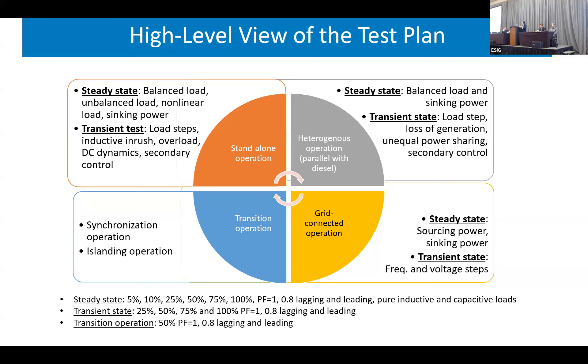We also have grid-connected operation. Industry wants to see how grid-forming inverters behave when connected to the grid. So we did a lot of grid-connected tests — how to control and dispatch the grid-forming inverter, how it can maintain system stability particularly for frequency response and voltage regulation. We also did LVRT tests, walk-off, phase jump, frequency scan to understand the inherent features, and varying grid impedance from strong to weak grid to see how grid-forming inverters behave better than grid-following.